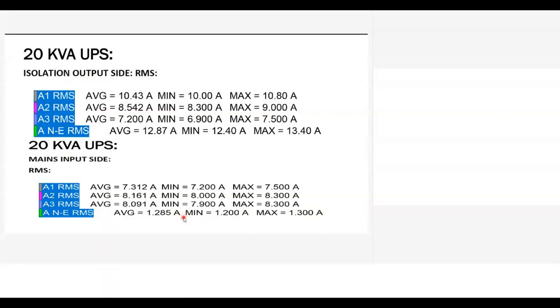The harmonics will remain. The only thing you get is an isolation function, so the earth neutral voltage you can reduce, or bring it to zero. But you don't really reduce the harmonics. Energy saving also is not there. You don't reduce the temperature in the UPS or in the computers. So it's very simple. You can use this zero impedance transformer, neutral compensator, neutral eliminator, whatever name we call it.